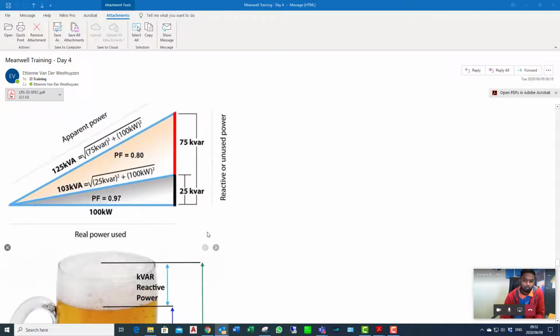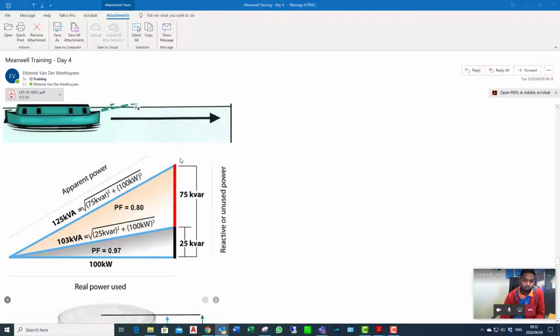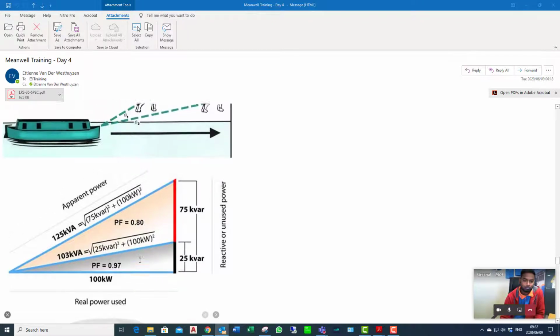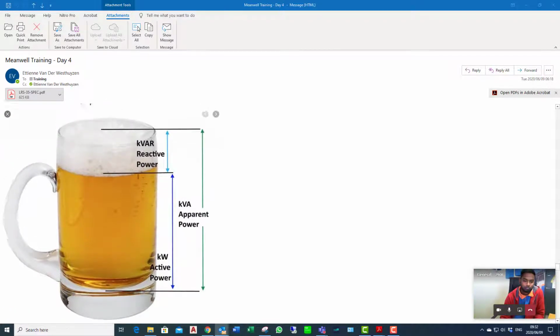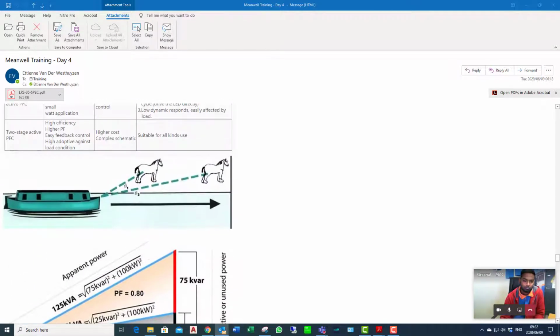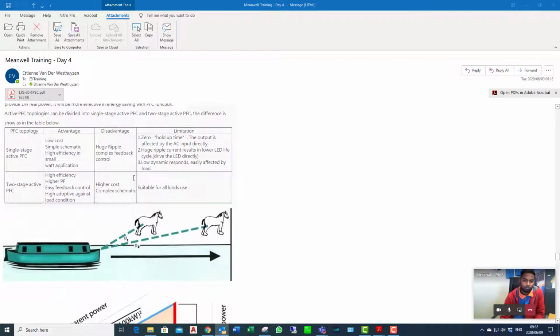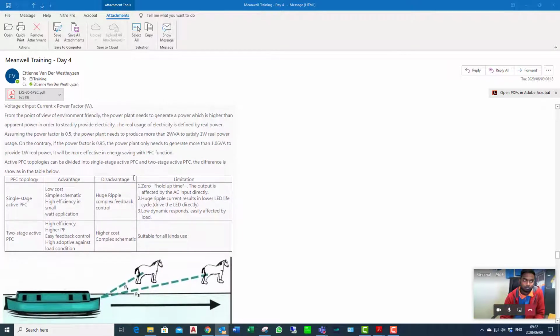And unfortunately you are being charged on the kVARs, okay, which is beautiful formulas, from Eskom. So if Eskom does give you a bill at the end of the month, they don't give you just the beer value of it, they charge you the reactive energy of it as well, because they actually need to generate a lot more energy at the power stations to be able to supply you that, and therefore that power factor has a huge impact.